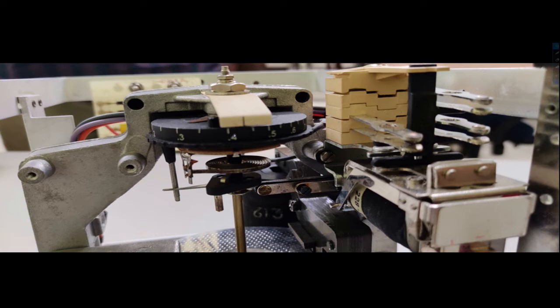Now sometimes we purposefully introduce some delay after the current exceeds the preset value. Why? Because most of the faults in the power system are transient in nature. It seems like a fault, but within 2 to 3 cycles the fault clears automatically, and it doesn't require any protection action, because the apparatus connected in the power system can withstand this high amount of current for 2 to 3 cycles. Nothing will happen. So that's why sometimes we put in some intentional delay.